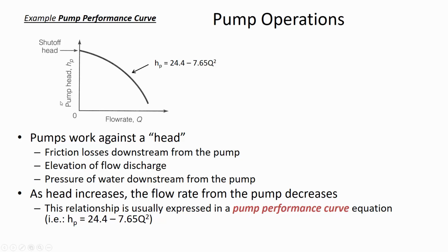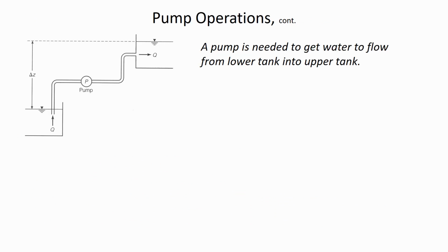Any questions about this? So we combine pumps with a system. Here's a representation of a system where we're pumping from a lower reservoir up to a higher reservoir. So this delta Z can be no more than the shutoff head for this pump. Otherwise, the system isn't going to even get 1 liter per second. But if the delta Z is less than the shutoff head, it will get some flow rate.